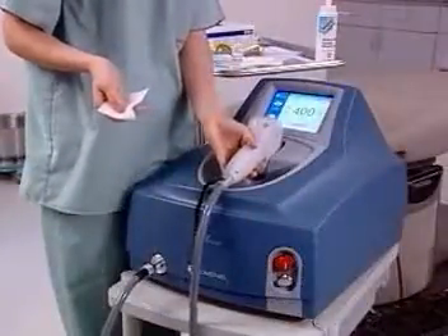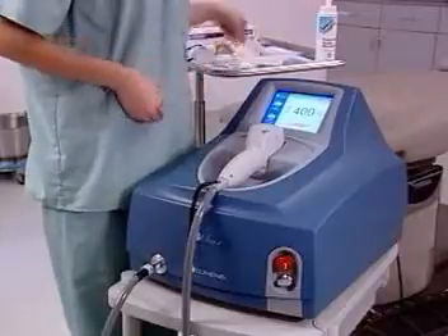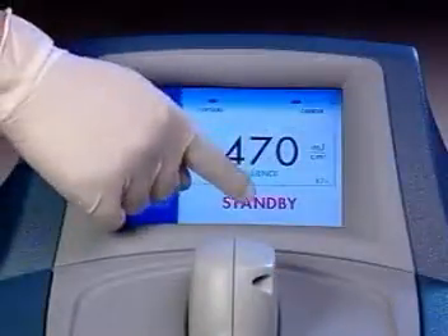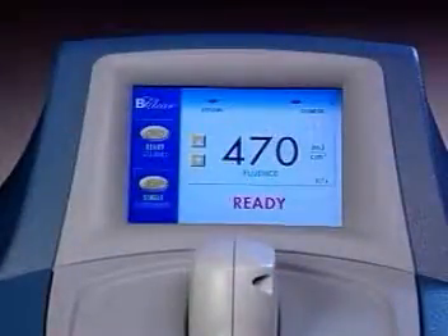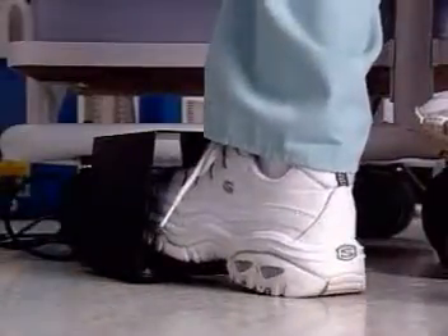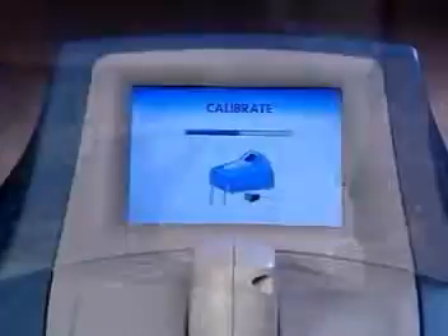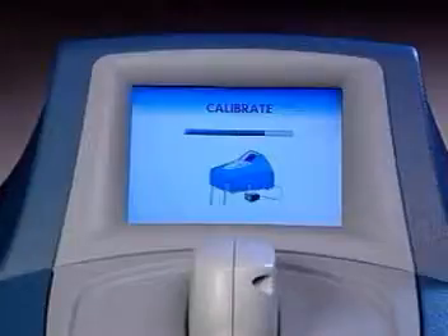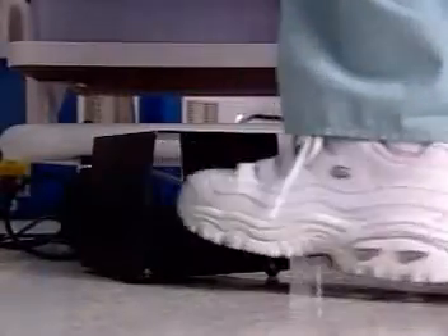Calibrating your system between patients follows a slightly different procedure. Select Ready from the treatment screen. Step on the foot switch and keep it pressed during calibration. Calibration progress is displayed on the touch screen. Release the foot switch when calibration is complete.